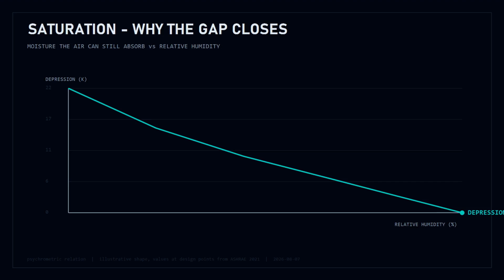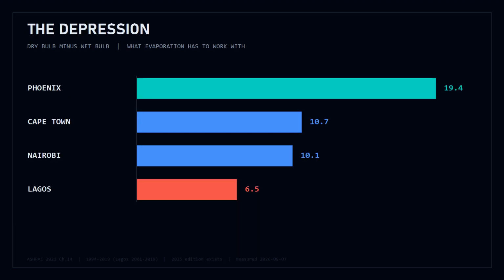The gap between them is called the depression, and it is the most useful number in cooling because wet bulb is a floor. No evaporative device of any size, of any design, makes water colder than the wet bulb of the air entering it, not an engineering limit. Thermodynamics. Hold on to the shape of that sentence because we are going to meet its opposite in a minute. A limit that is an engineering one, and which behaves completely differently.